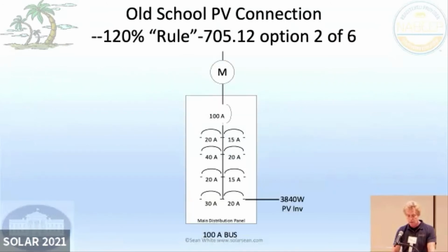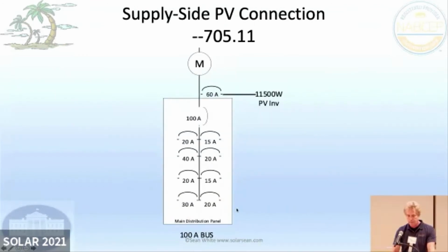So this one is the 120% rule that I talked about. 16 amps times 240 volts for your house is 3840 watts. And that goes on a 20 amp breaker, because 16 amps times 1.25 for safety is 20 amps. And they go on opposite sides. So there we go. This is a supply side connection. We're going between the meter and the main breaker, and you can put almost as big as you want there.